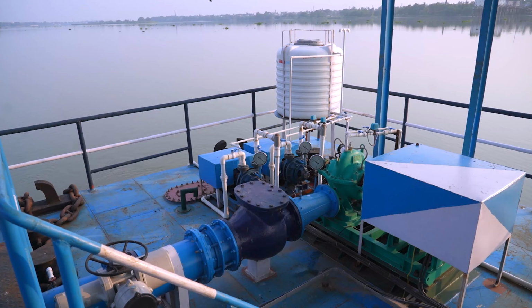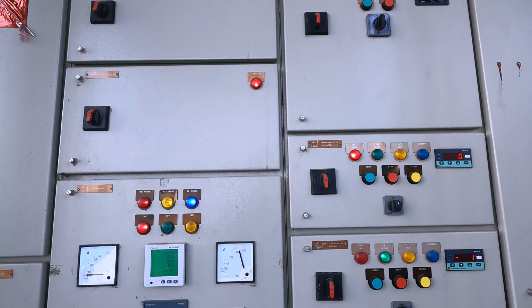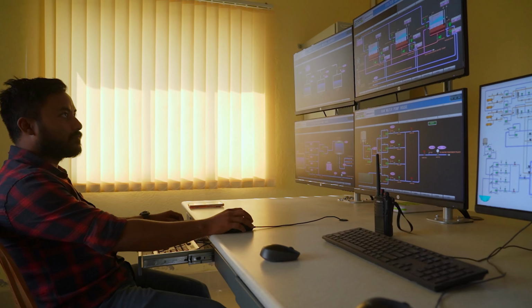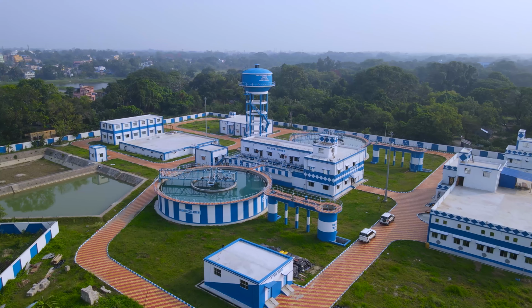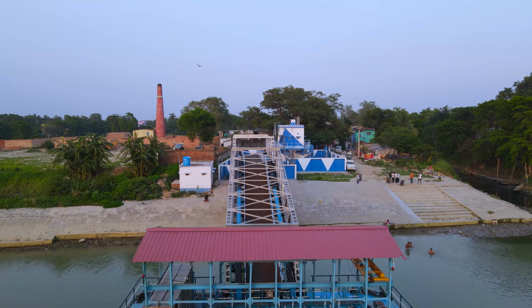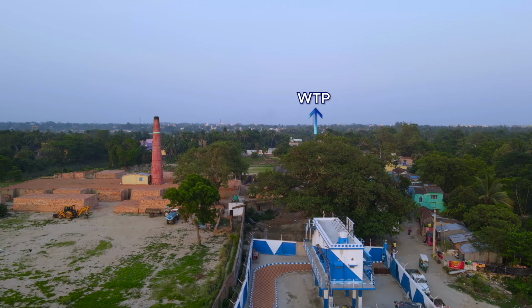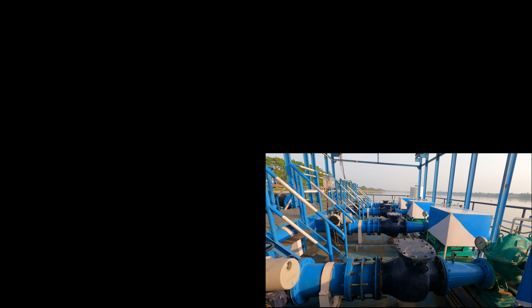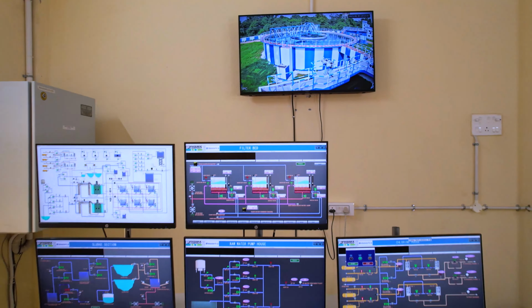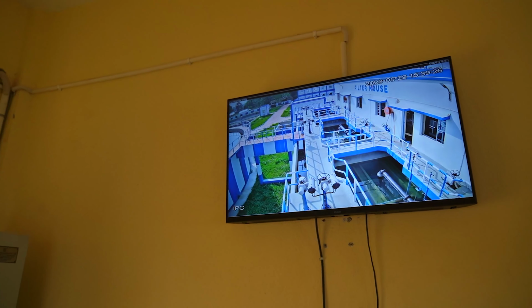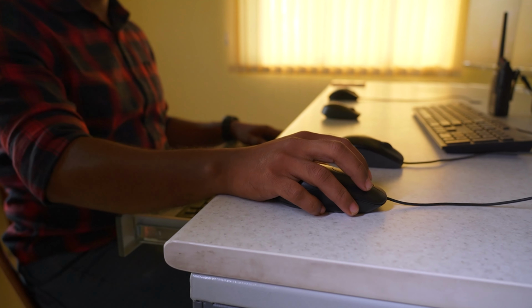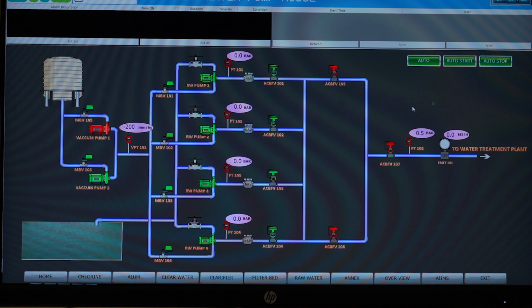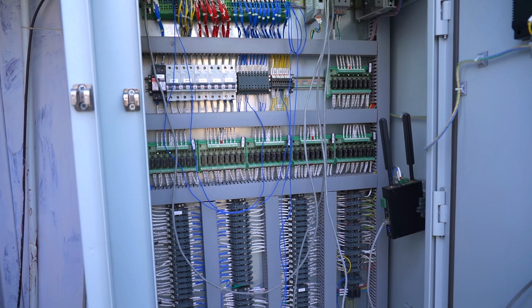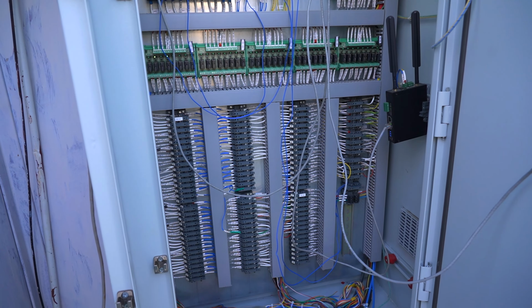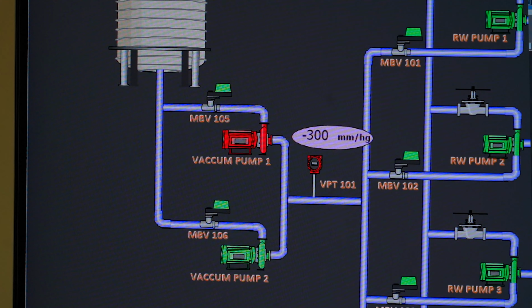The raw water lifting plants are being operated, controlled and monitored through SCADA arrangement on a 24/7 basis from the central SCADA room at the WTP campus, situated 12 km far away remotely through wireless communication. There are 4 CCTV cameras installed at 4 strategic points for surveillance. The operator sitting at the main console in the annex building gives a command to start the vacuum pump remotely. The RTU at the intake pump house receives it via wireless modem and initializes the vacuum pump. When the required vacuum is reached, it automatically starts the main pump.